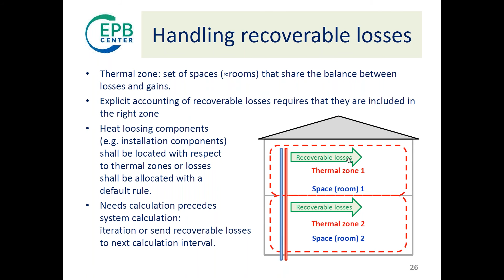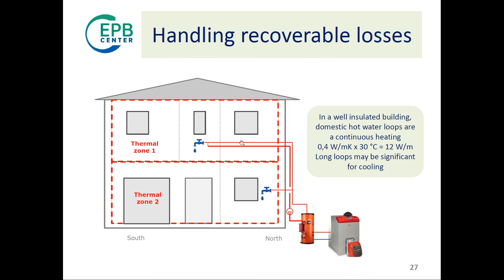So you have to identify where the components of your system are located. This is highlighted by the general standard EN ISO 52000, but it's a feature that can have consequences and needs to be known when using the TC228 standard. So we identify recoverable losses, and you have to attribute them to the right thermal zone. Just think about domestic hot water loops which end up heating your building in summer — not a very good result.